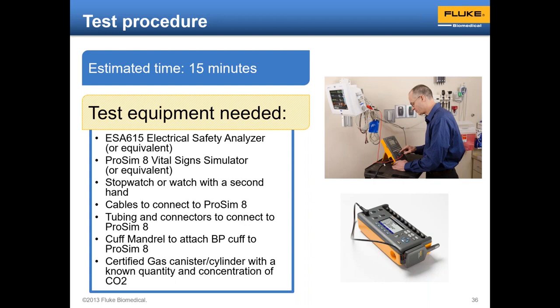An electrical safety analyzer, a good patient simulator. You still will need a stopwatch with this, or a watch with a second hand, and you'll need tubings and connectors appropriate for connecting to the patient monitor, and a cuff mandrel or something appropriate to wrap the blood pressure cuff around for NIBP testing. If the patient monitor includes any end tidal CO2 or multiple gas monitor function, you need the appropriate certified test gases to make sure that that function is properly responding to the patient's exhaled gases.